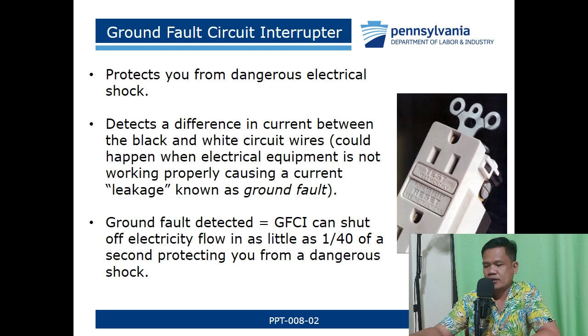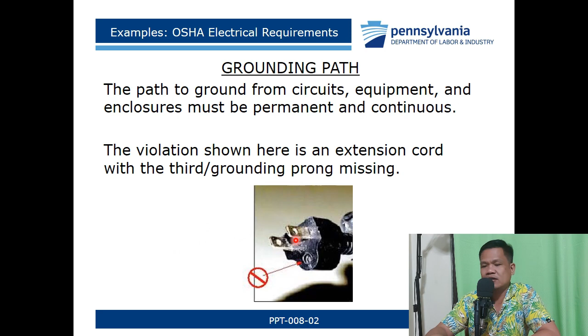Now, these are some examples of the OSHA electrical requirements. They require a grounding path. The path to ground from circuits, equipment, and enclosures must be permanent and continuous. The violation shown here is an extension cord with the third grounding prong missing. Sometimes the grounding prong is removed so the cord can be plugged into a normal outlet.